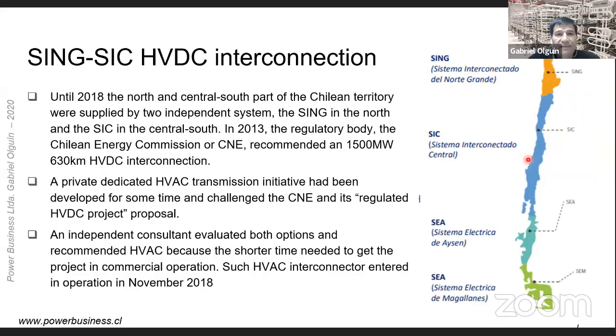Another HVDC initiative was the interconnection between the 2 largest systems we had. Before 2018, the Chilean power system had 4 independent electric power systems. The SING in the north and the SIC in the central south of Chile were the largest of the 4 systems. The Chilean government had the idea of interconnecting these 2 large systems to take advantage of sharing reserves and energy exchange. The SING in the north is mainly thermal, while the SIC is hydrothermal. In 2013, the government finally promoted the interconnection of the 2 systems using high voltage direct current transmission, mainly because of the length of the line.